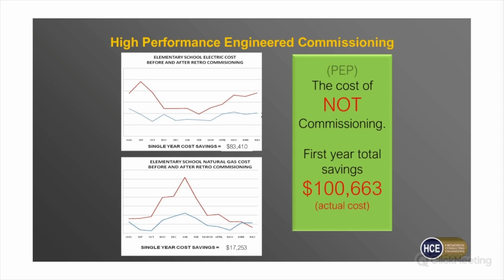Here's a bit of an extreme example. We had a client whose energy for their elementary school was really high in their opinion. So we went and reviewed some items with them. One of the things that had happened was the controls and the units weren't set up correctly to listen to the control system. We asked them to check if their stuff was running at night. They said the control system said it was off. So we drove by the elementary school in the middle of the night, and all the air conditioners were running.